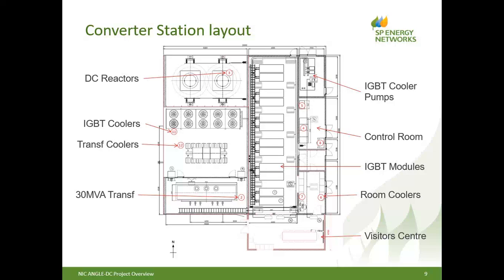The main event is in the IGBT module room, which you can see runs down slightly right of centre. Obviously that's all water cooled, and the cooling goes through the fans and the radiators. It's an air conditioned room, a dust-free type environment, etc. And then to the right hand side is where the ancillaries are: the cooler pumps, the control room, which will have the desk with the workstation in, which gives us the opportunity to monitor and operate the DC link. And we've also got coolers and a DC switch room in there as well.